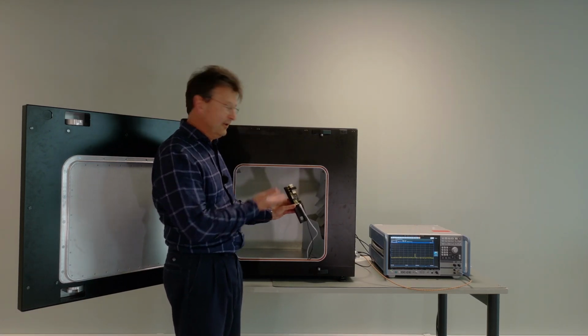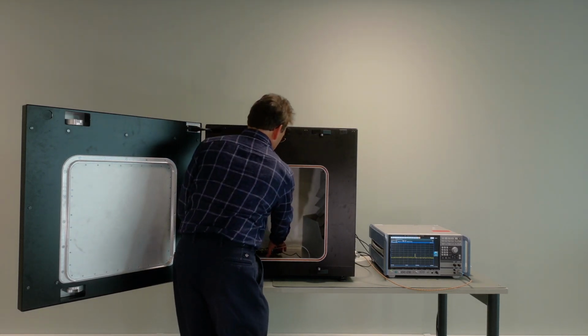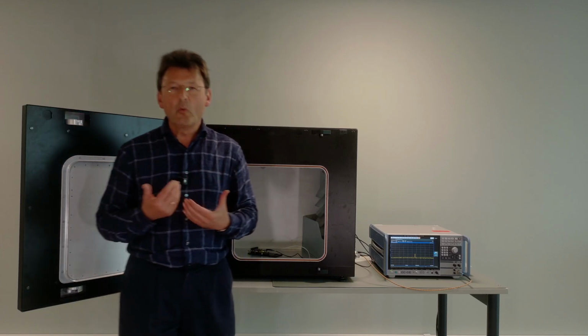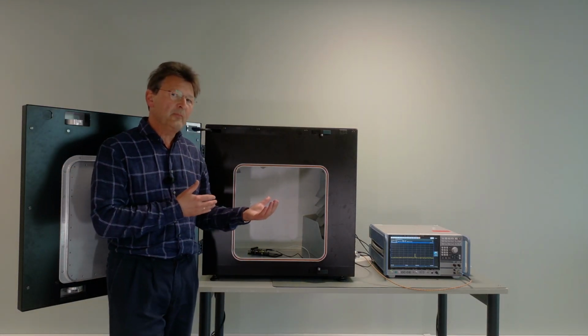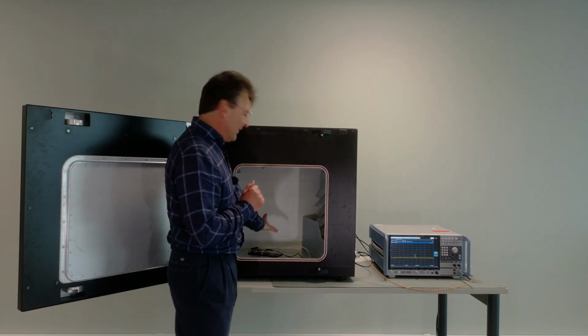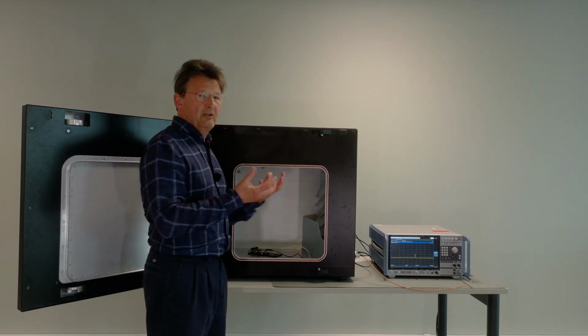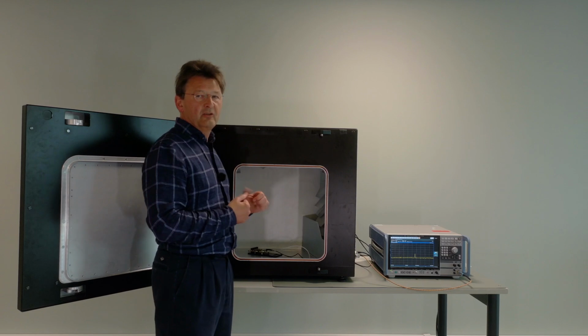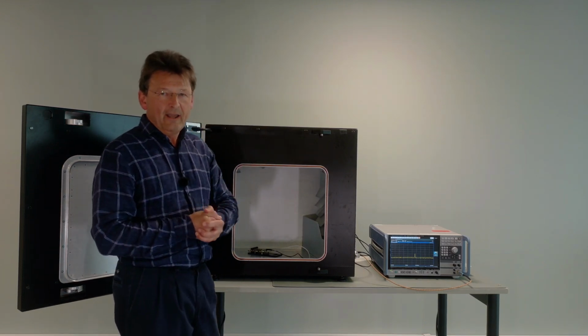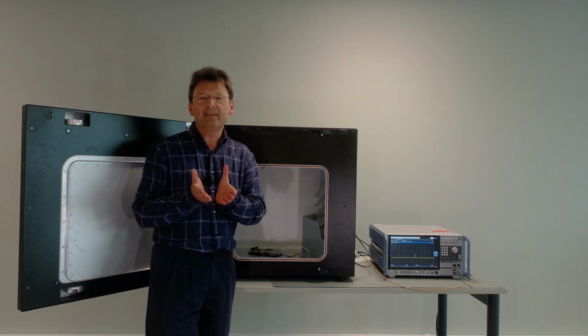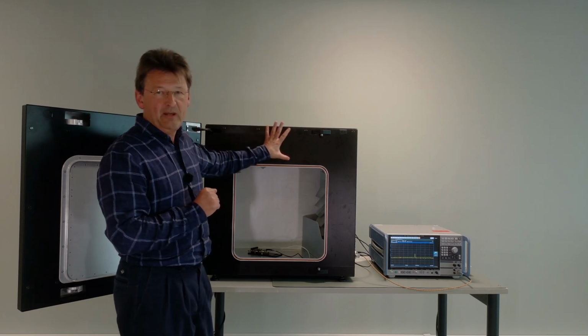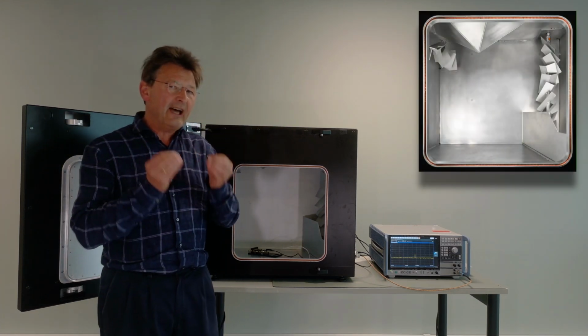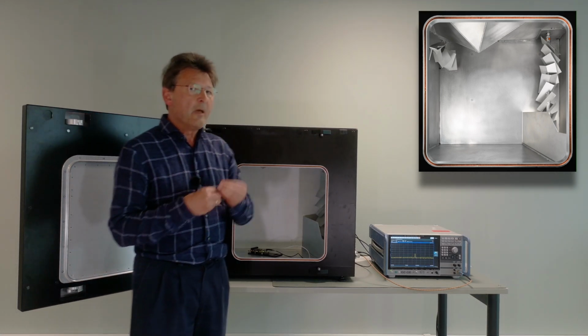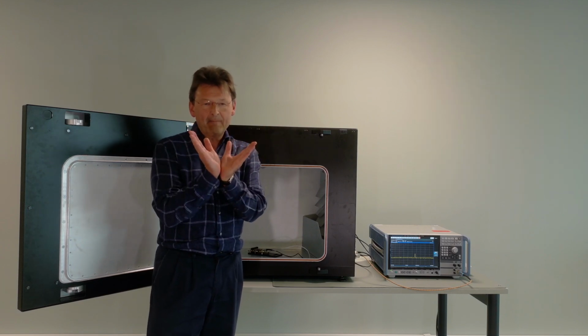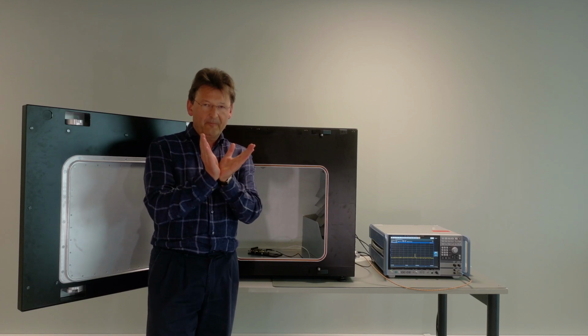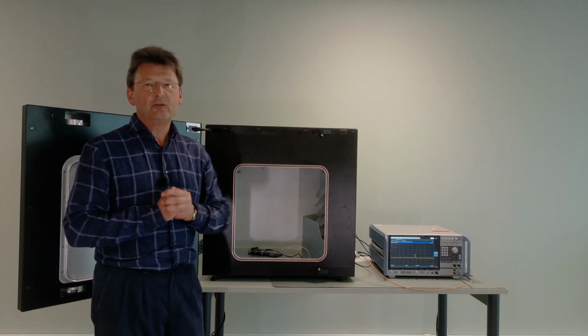We can put this device in the chamber at almost any location. And that's very handy, of course, because you don't have to worry about alignments in contrast to, for example, the anechoic chamber. Now, what's important though is that the direction of the radiated fields is upwards to the ceiling of the chamber. Why? Well, we want to avoid direct reflection to that device under test. And the top of the chamber has been designed specifically to minimize the possibility to get a direct reflection. And in fact, between a steering angle of -60 to 60, that direct reflection should be avoided. So that's a kind of an important thing to take into account.